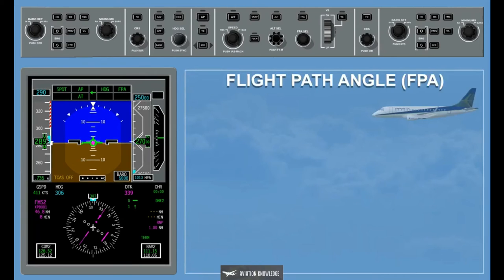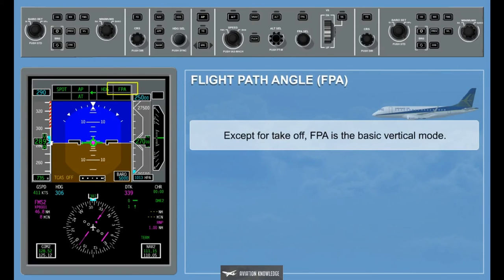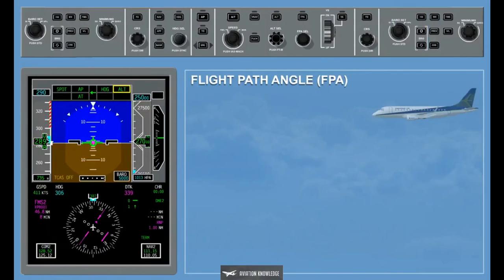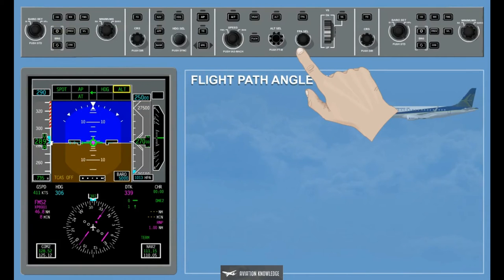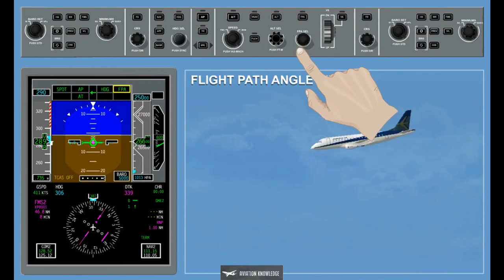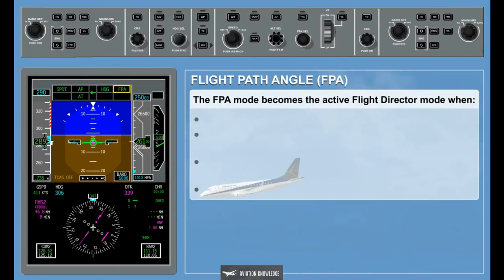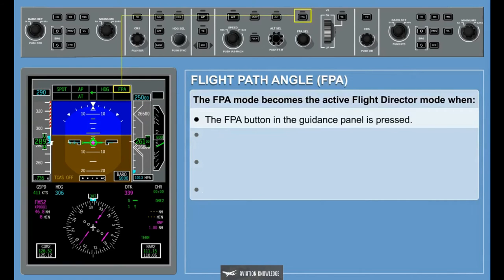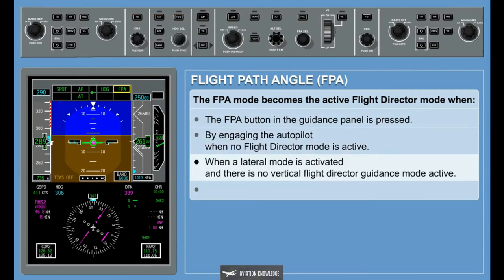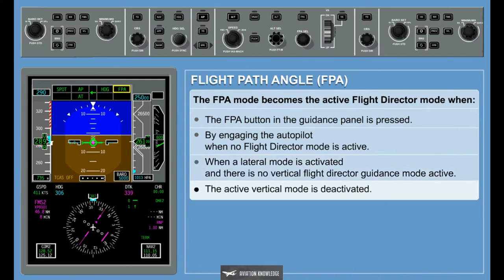Flight Path Angle, FPA: Except for takeoff, FPA is the basic vertical mode. When FPA is active, the flight path reference line is displayed. Pressing the FPR button in the display controller panel displays the flight path reference line regardless of the active vertical mode. The flight path angle can be selected via the FPA selector knob on the guidance panel. The flight path angle mode becomes the active flight director mode when the FPA button is pressed, by engaging the autopilot when no flight director mode is active, or when a lateral mode is activated and there is no vertical flight director guidance mode active.